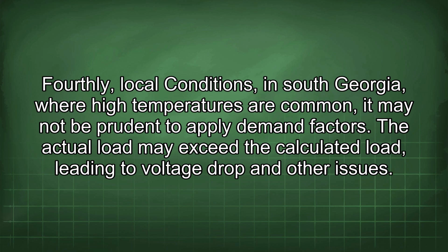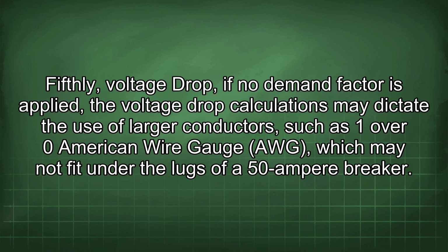Fourthly, local conditions. In South Georgia, where high temperatures are common, it may not be prudent to apply demand factors. The actual load may exceed the calculated load, leading to voltage drop and other issues. Fifthly, voltage drop. If no demand factor is applied, the voltage drop calculations may dictate the use of larger conductors, such as 1/0 American Wire Gauge (AWG), which may not fit under the lugs of a 50 ampere breaker.